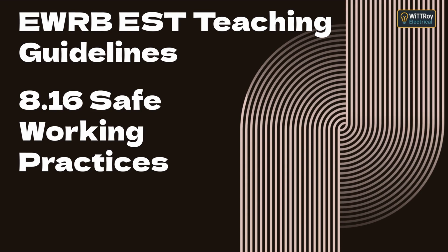Dead testing is done with the power isolated and proved dead. Live testing is done with the circuit energized, but only when absolutely necessary. Here's how to explain the difference out loud. Dead testing checks that the installation is wired correctly, earthed properly, and safe before the power is turned on. Examples include continuity testing, insulation resistance testing, and polarity testing.